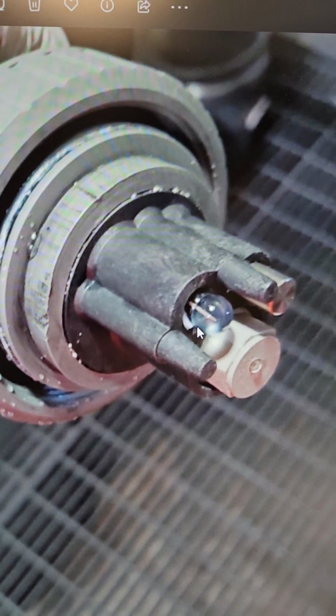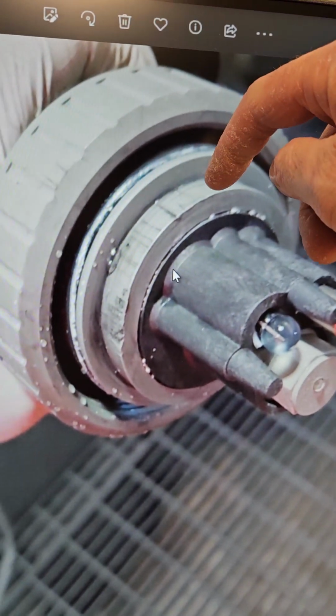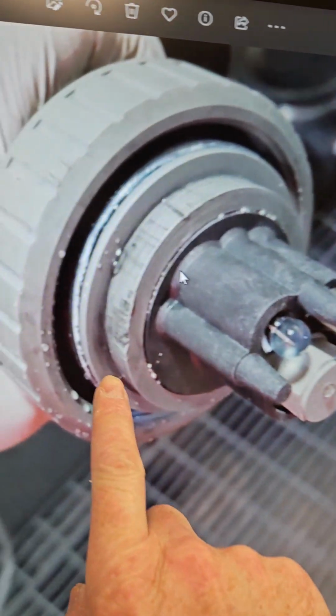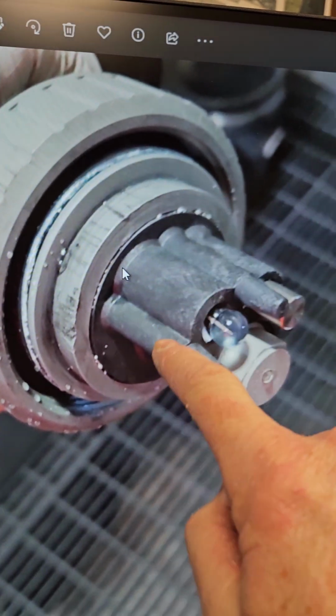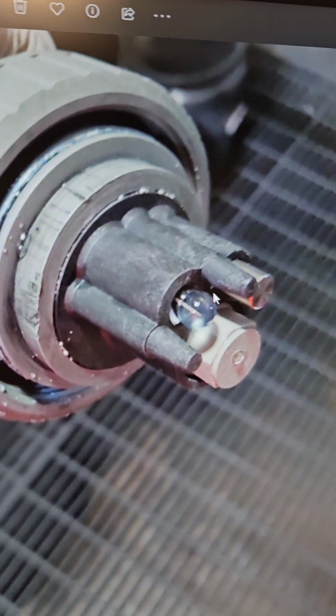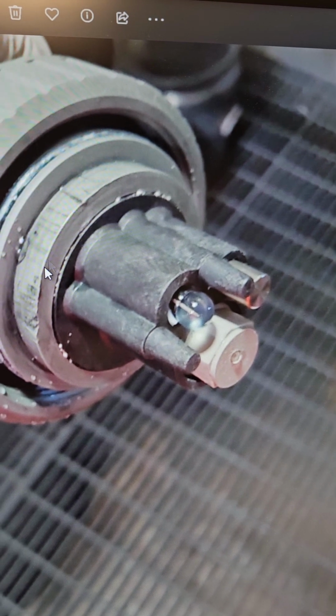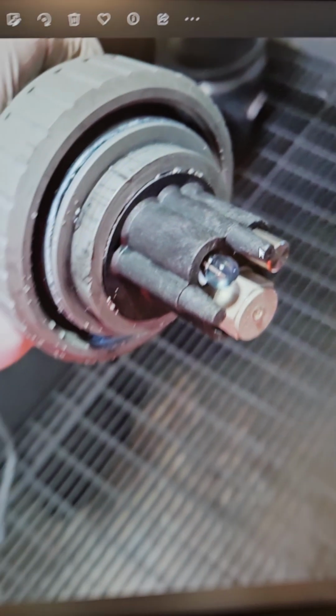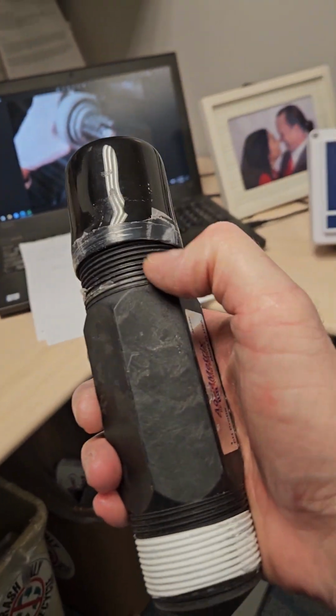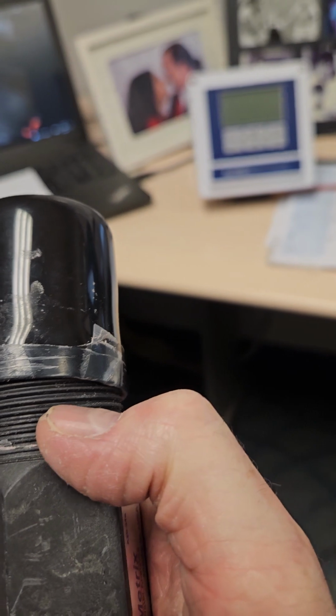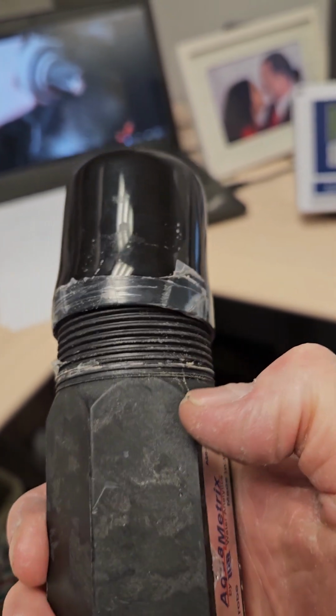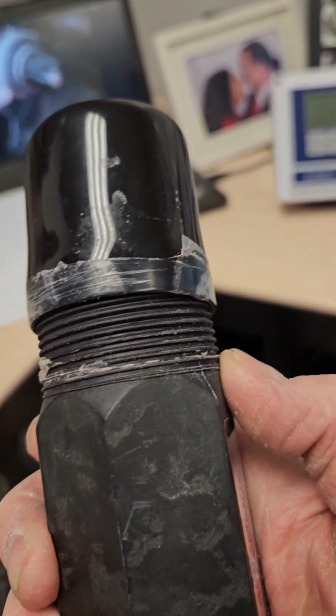If you notice, there's the probe that sits down into the water. You have to use a channel lock on this very small area to actually screw this on with pipe dope. If I'm using Aquametrics probes, I actually use RTV silicone instead of pipe dope, because their mold is very old, so the threads are not very accurate, and they don't really seal. Even with pipe dope, they leak a lot. So I ended up just putting RTV silicone on, and when you take it out, it beads up and crumbles and comes apart, so you don't get a leak on those probes.